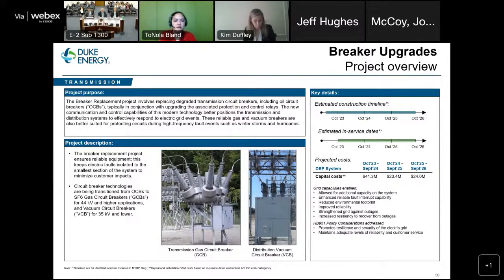I'll move next into our circuit breaker upgrade project. This upgrade project is targeting assets that are at the end of life. Particularly, we're targeting oil circuit breakers. Oil-filled circuit breakers are a legacy technology. It is an oil-filled tank. That oil actually arrests the fault and the arc gases and extinguishes the arc when a circuit breaker opens or closes. It's an outdated technology, and these breakers are prone to failure.